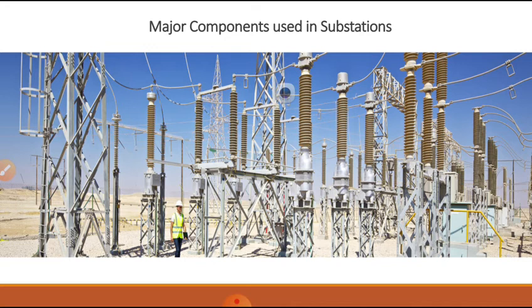Now you can see the line diagram we have seen. First, here is the real time substation. If you see the start, here is the lightning arrester, before entering the transmission line. So the receiving equipment is the lightning arresters. After that we are going to use the CVT, capacitor voltage transformer. It also senses the surges that come. It gives the potential voltage, and we also use it for PLCC purposes, for dispatch.